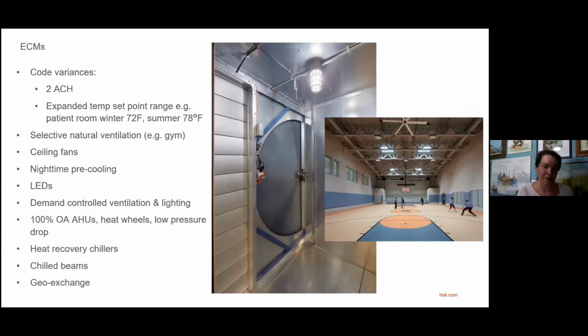For the ECMs, we asked for some code variances, like 2 air changes in certain spaces since this is not an acute care facility. We did not need a higher air change level. We expanded temperature set point ranges with things like ceiling fans, select natural ventilation in certain spaces like the gymnasium, and did a nighttime flush pre-cooling of a lot of the facility.